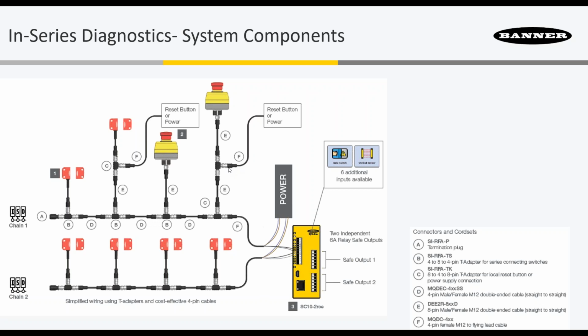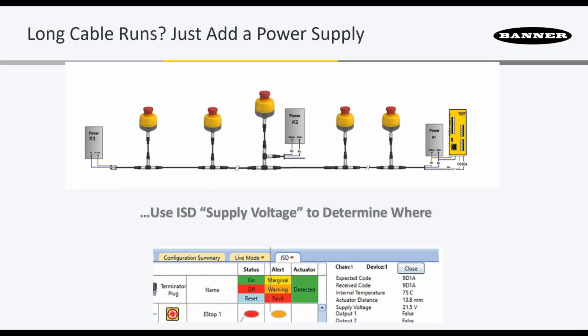This same T connector is also a way to add additional power to a chain, since our real limitation on ISD is the 32 devices. If you need to add incremental power - say you have a long run or a lot of devices - you can either replace the termination plug at the end and connect another power supply there, or use a T-connector somewhere in the chain to add power. What's really cool about ISD is that it can tell you exactly where a voltage issue is located in the chain, so you know where to add power. It's a really neat system.